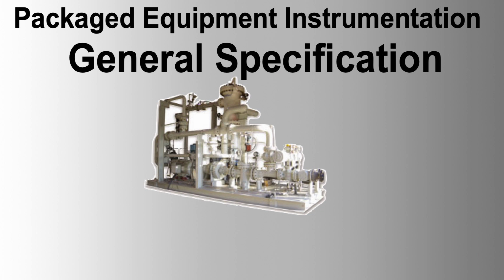Instruments must be numbered according to the piping and instrumentation diagrams used throughout the job, with deleted item numbers not reused. The package should be designed for failsafe unmanned automatic operation unless specified otherwise by the company. Package panels shall be PLC-based, rated to IP66, located in the field, and suitable for hazardous area classification to Zone 1, Group IIA/IIB, and Temp Class T3.